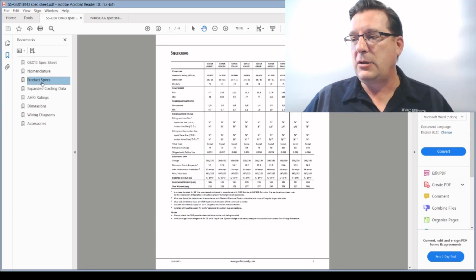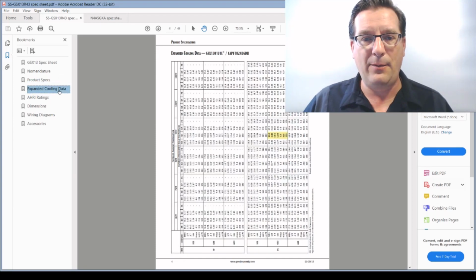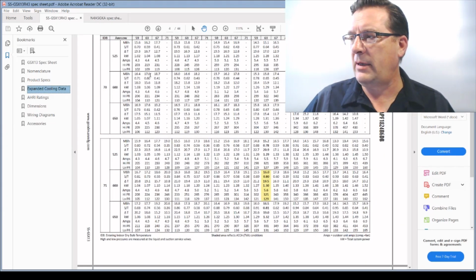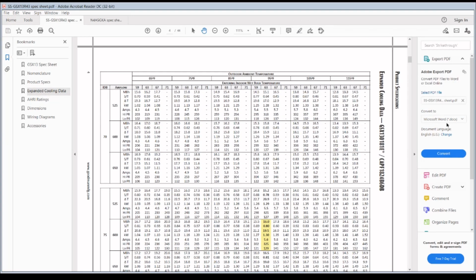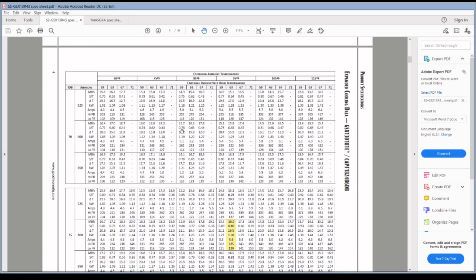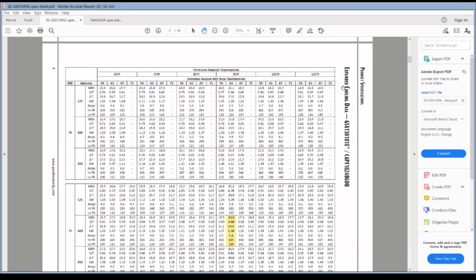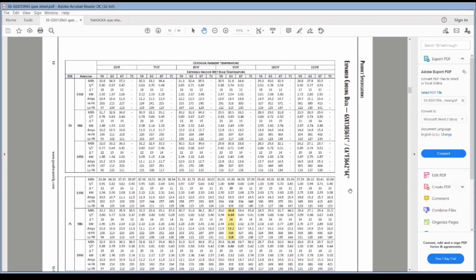I'm going to jump forward to the expanded cooling data. That's what we want. So let's shrink this down a little bit and see what it is that we're looking at here. We'll move this out of the way. Over here on the right hand side, it gives us our expanded cooling data for the GSX13 and various sizes and various coil combinations. So the first page here details the GSX130181E combined with an evaporator coil of a CAPF1824B6DB. That is a mouthful. Let's go ahead and stick with our 3-ton idea, because a lot of folks are pretty familiar with 3-ton systems.